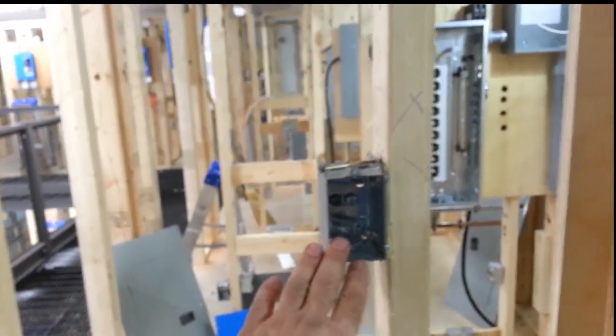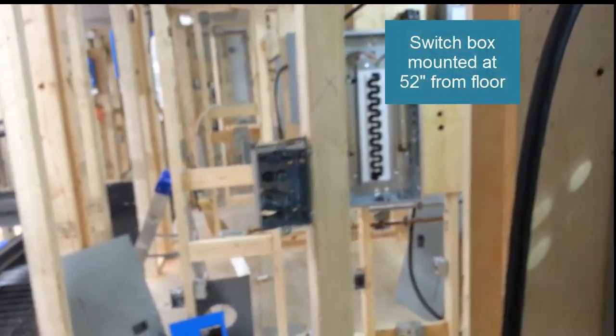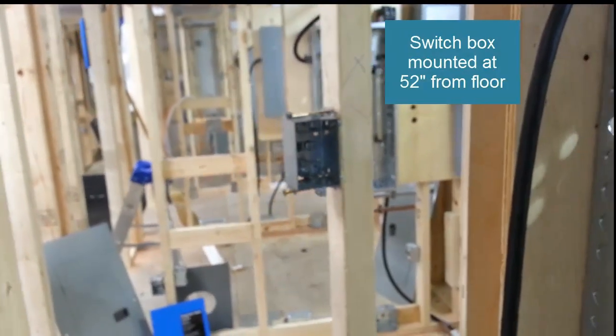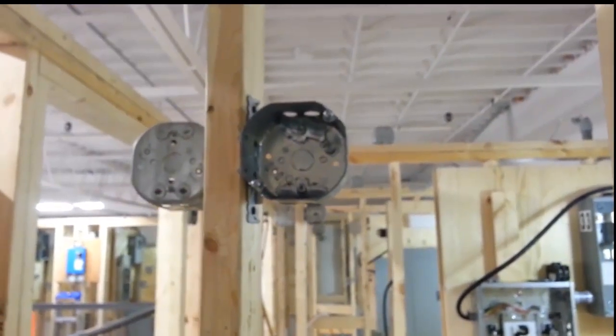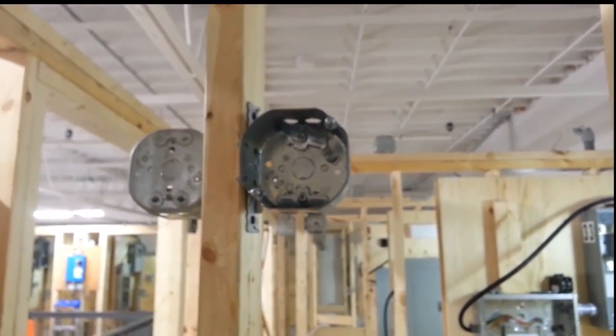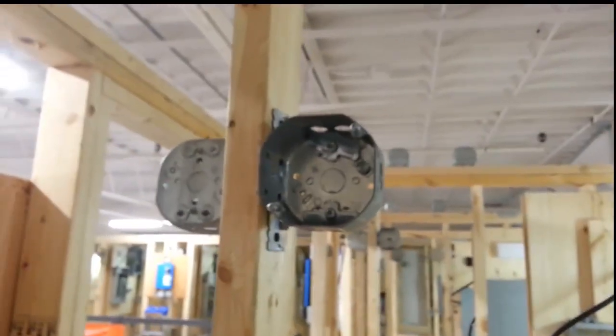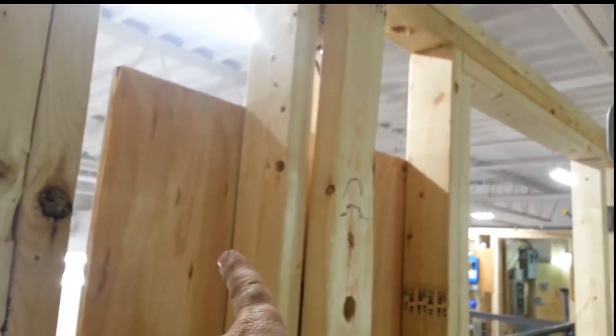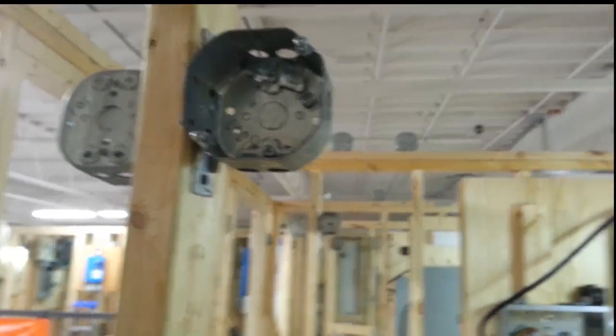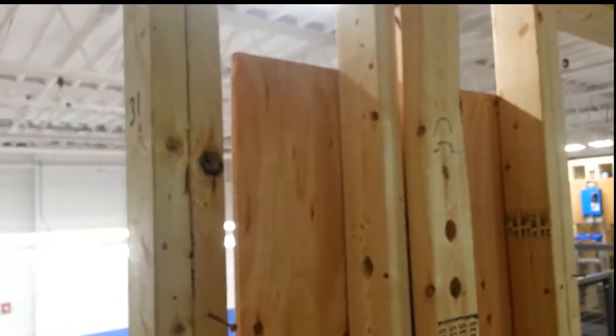Each student will work in their own cubicle. They will place a low voltage switch in a switch box mounted at 52 inches just like we learned in last intake for regular switches. And you will also need a round box for a light. So you will need a keyless light bulb. The 14-2 will go from the light bulb to the unit on the back of this plywood. If you are working in other cubicles, you may need to go from your light all the way across and come along stapling your wire to go to your control panel. So in total, we will have four 14-2s coming from two cubicles back to our panel.